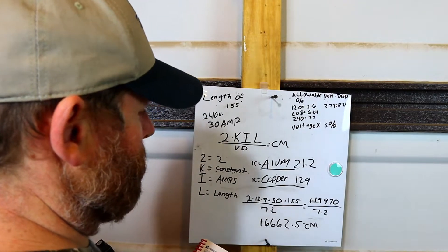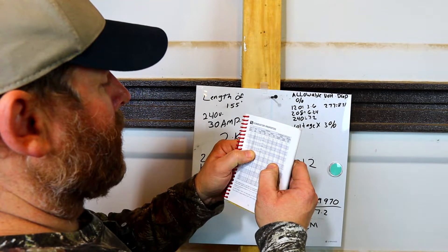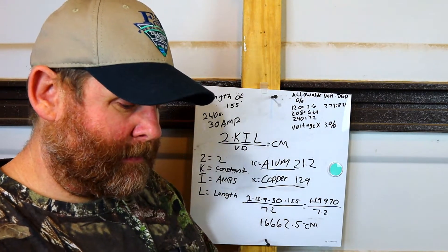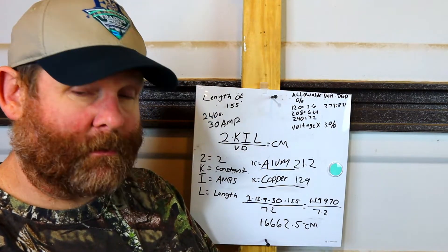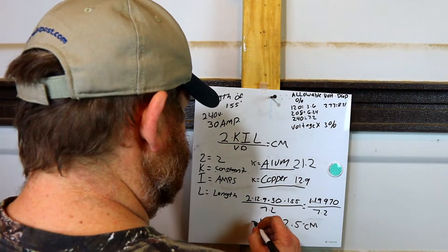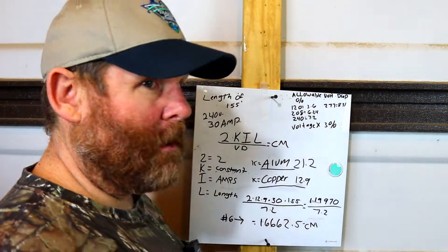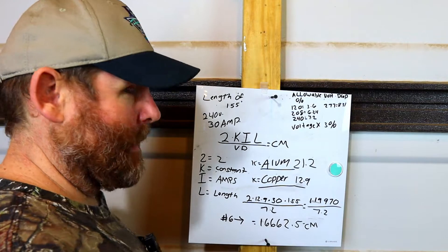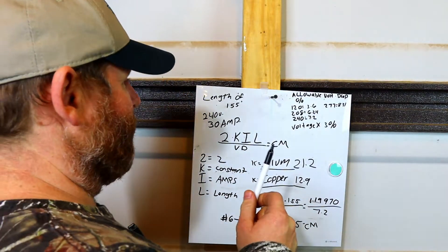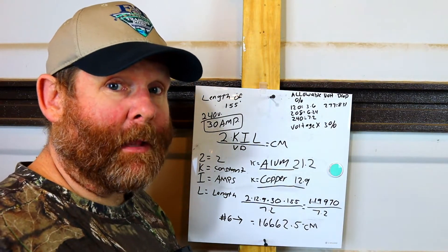So we know our number is 16,662 circular mills. Looking that up, it jumps from 16,510 — which is number 8 wire — to 26,240 — which is number 6 wire. That tells you that you have to go with number 6. So this equals a number 6 wire. Number 6 is obviously not rated just for 30 amps, but I needed to go up to number 6 gauge wire because of the voltage drop over that distance.